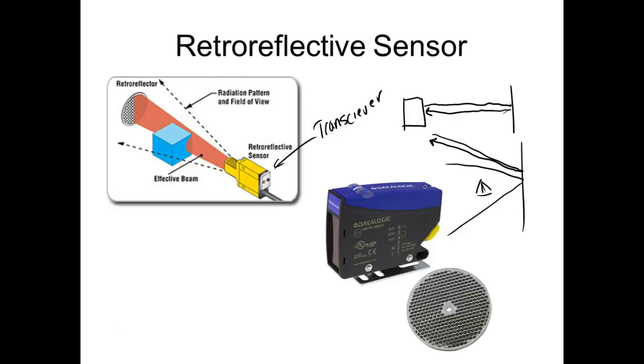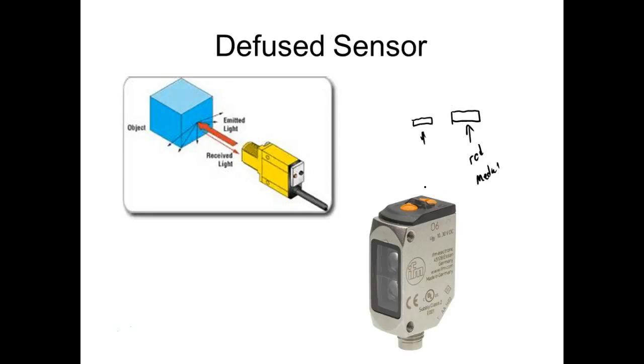Now there's a variation of this that the book doesn't talk about. It's a diffuse sensor, but it's called a definite reflective diffuse sensor. It depends on reflective light, but they mount the transmitter and the receiver at angles with each other. If the object is at a certain distance, it will hit the receiver. If it's too close, it would bounce up into here and miss the receiver. If it's too far away, it would bounce that way and miss the receiver.